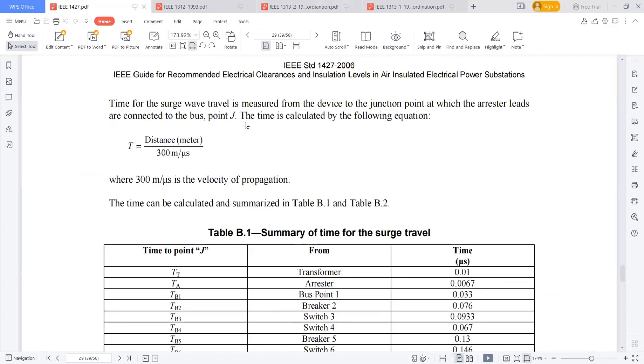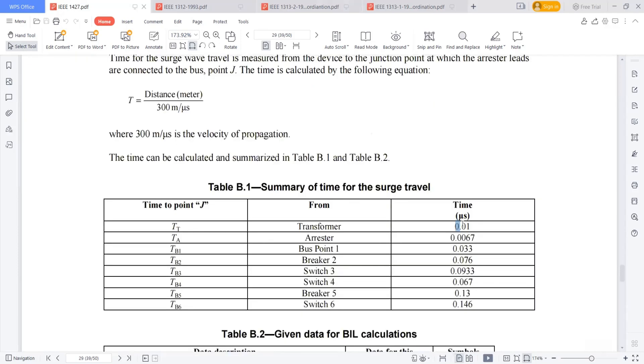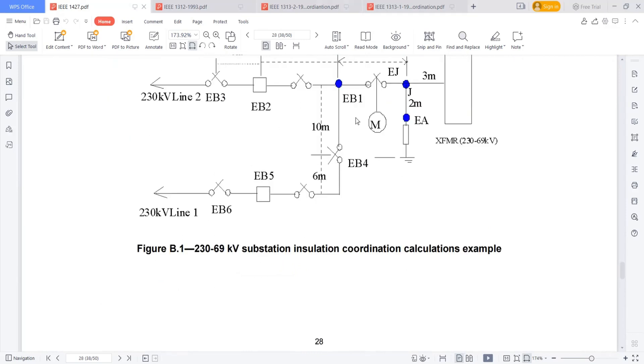I am calculating if suppose a surge occurred, then what time it will take to reach the junction point. So obviously it's distance divided by velocity. What is the speed? 300 meter per microsecond, velocity of propagation. So what is the distance divided by this? Suppose if I'm talking about the transformer, it's 3 meters. So 3 by 300, which gives me 0.01 microsecond. So like that, I have calculated that time. Suppose a surge occurred here, how much time it will take to reach the isolator, to reach the lightning arrestor to suppress this surge.